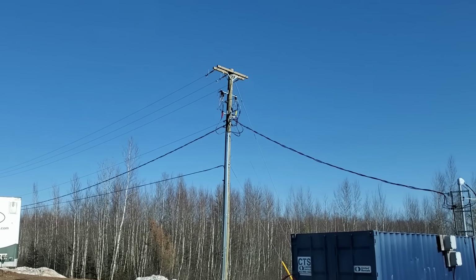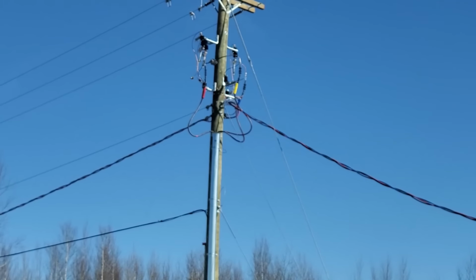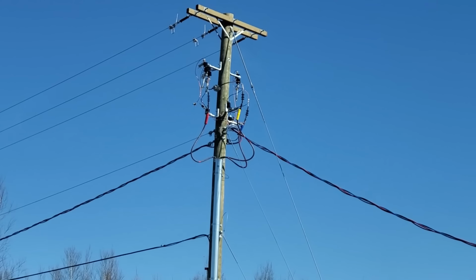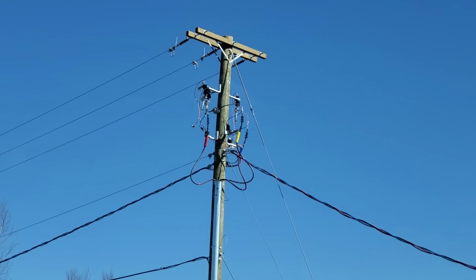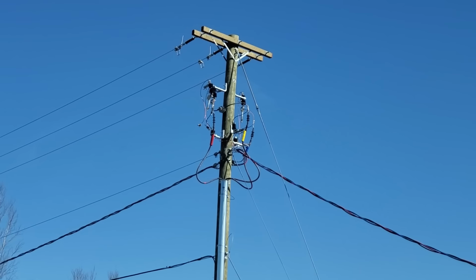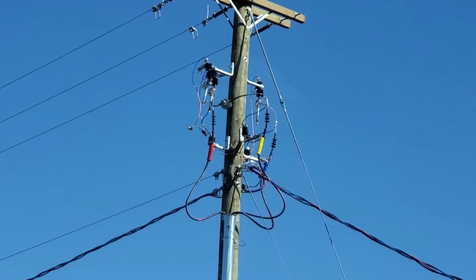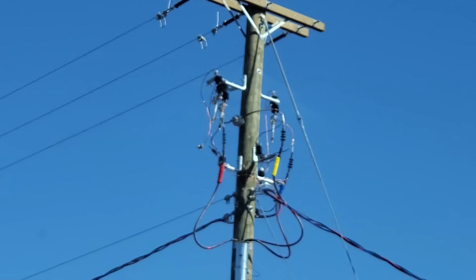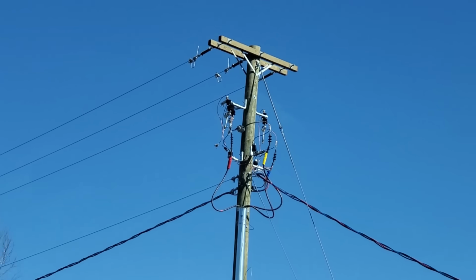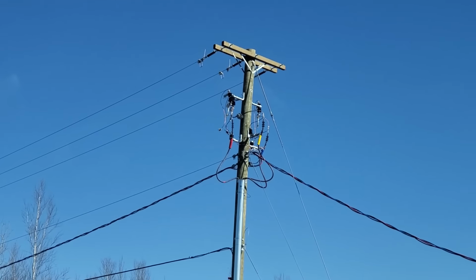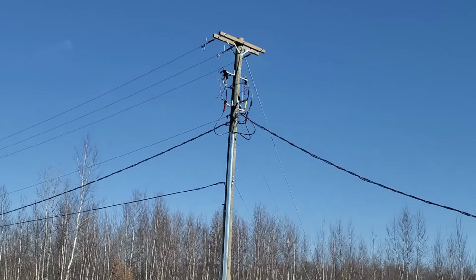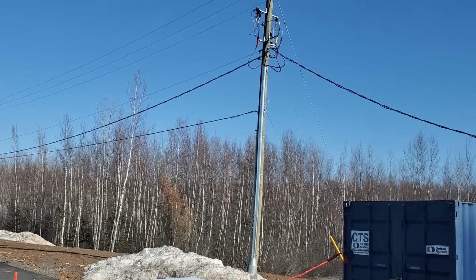This is the pole here that's going to be energizing the pad mount transformer. There were some crews on site that just pulled this underground and framed this pole up yesterday. You can see the cutouts are not currently tapped on, so I will have to get my truck in there, install those risers, and close that cutout in, which will energize the pad mount transformer.